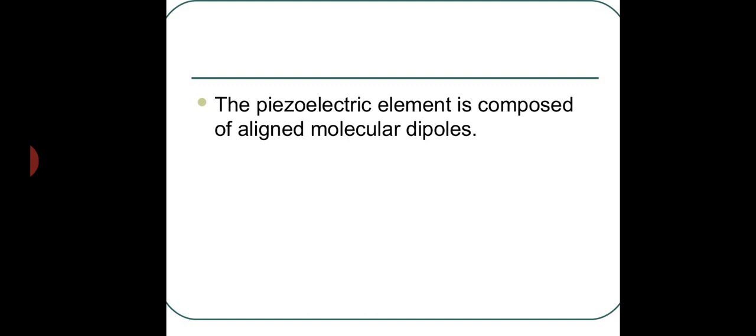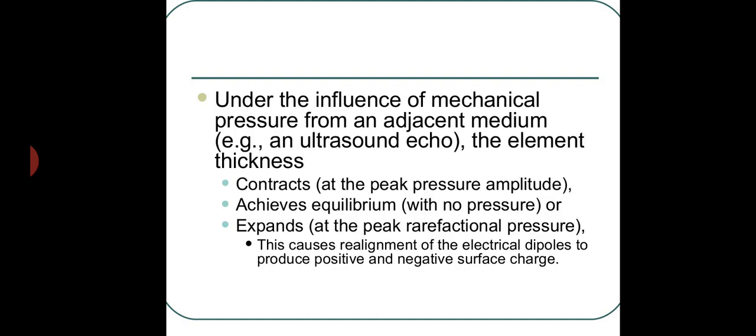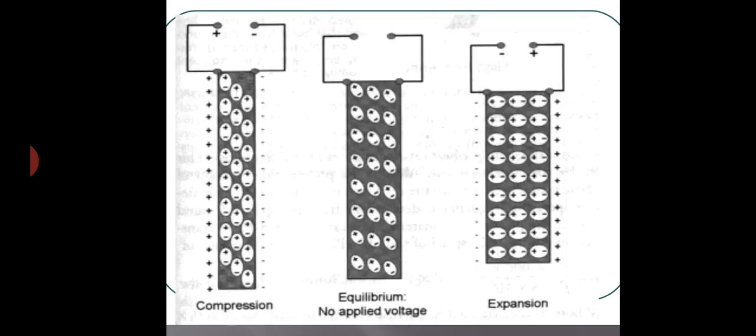The piezoelectric element is composed of aligned molecular dipoles. Under the influence of mechanical pressure from an adjacent medium, the element thickness contracts, achieves equilibrium, then expands. This causes realignment of electrical dipoles to produce positive and negative surface charges. Here is the example.